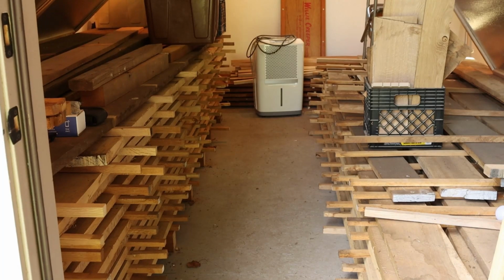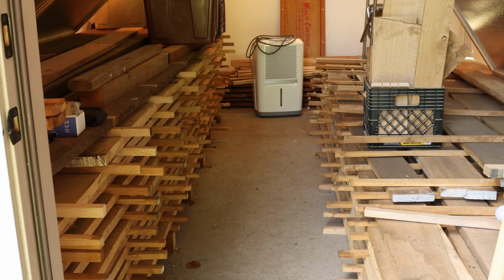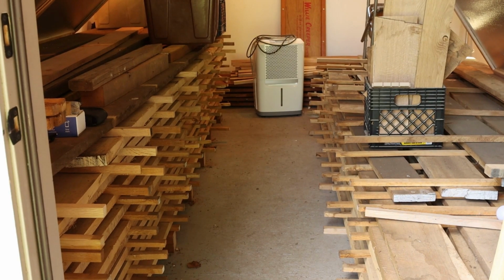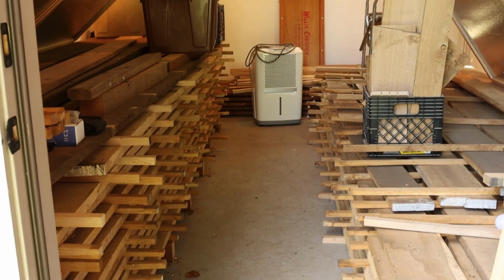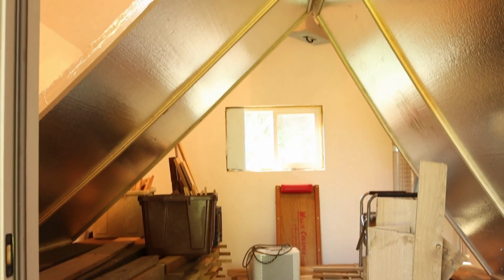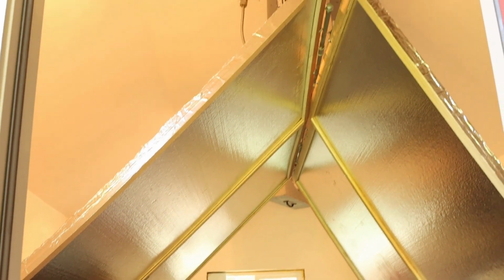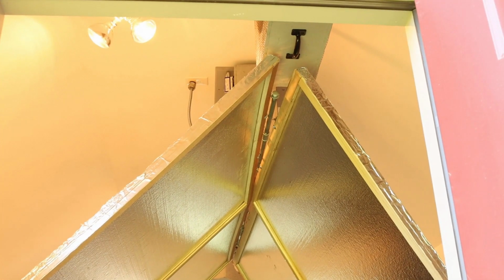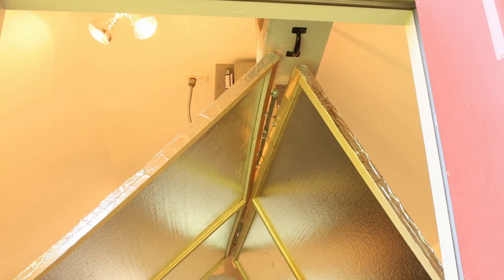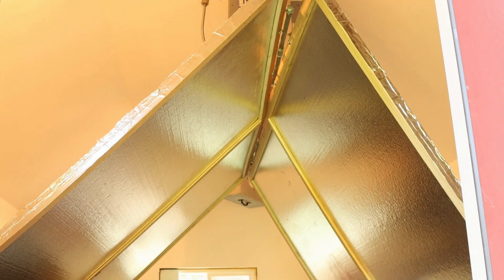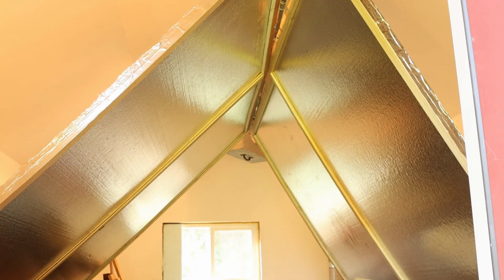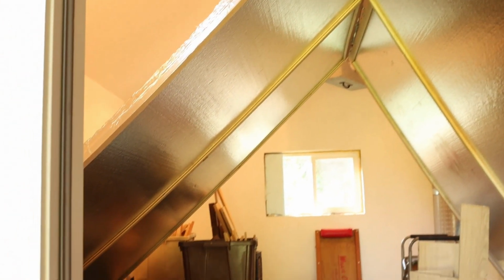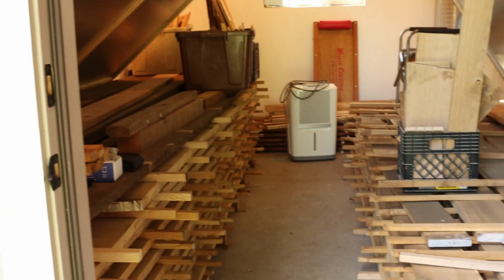So the overall layout of the kiln: we've got stacks to the left and right with a walkway down between. There's a household dehumidifier, a fairly large size, to extract the moisture from the air. And then up above we have overhead fans in fan shroud boxes. We've got 4 of them there, as well as large foam baffles to direct the airflow down around the lumber in kind of a circular pattern.